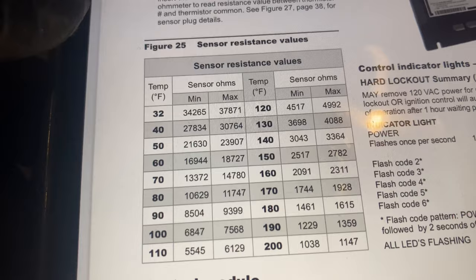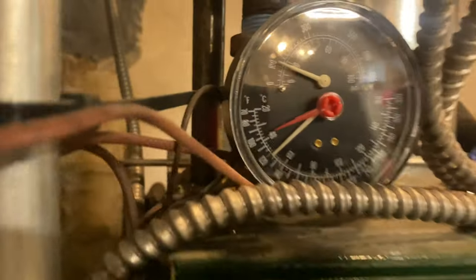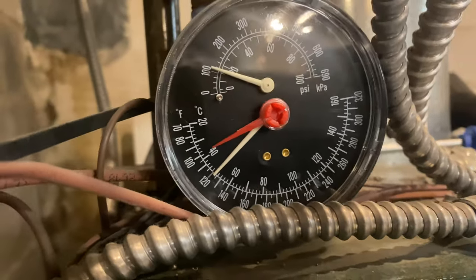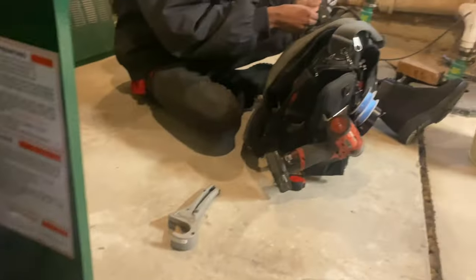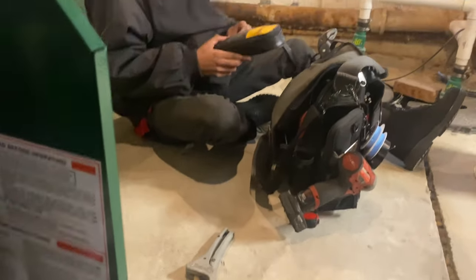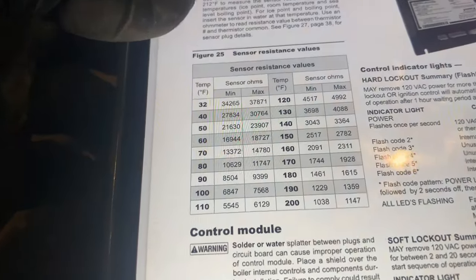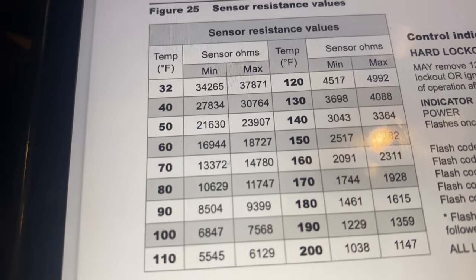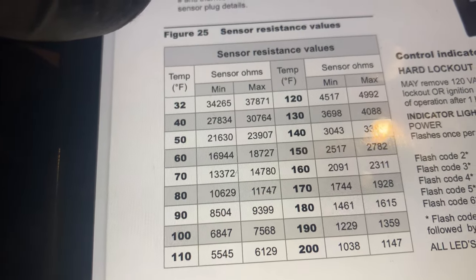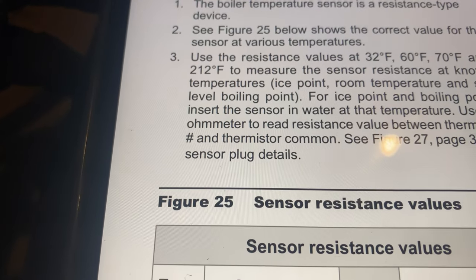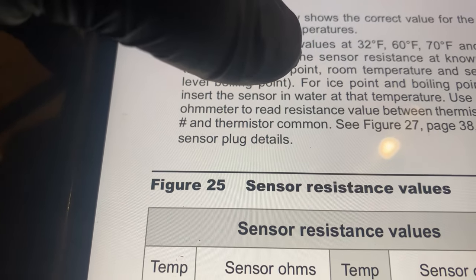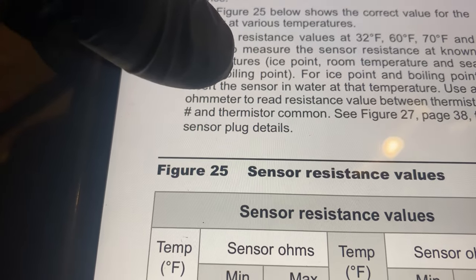If we look on the previous page, page 37, there are our resistance values. Our boiler temperature is around 120 degrees. Limit is flashing - no, just take the thing out of the pouch, let's unzip it. Okay, so we're at 120 degrees, so our minimum should be 4517 and 4992. And we're going to test the resistance value between thermistor number and thermistor common.